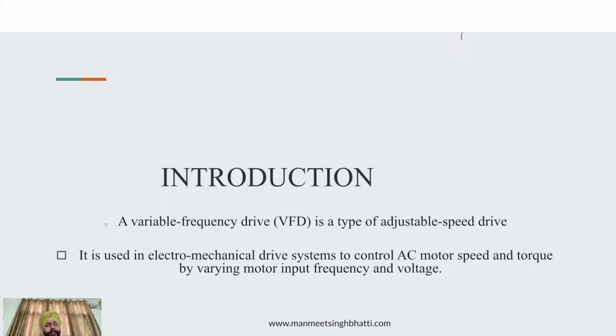As the name suggests, it is going to change the frequency of the complete power which is being given to your AC motor, and that way it is going to control the speed. So a variable frequency drive, as the name suggests, is only going to change the frequency of the power. Based on that, the speed of the motor is being controlled. So that's the basics of the variable frequency drive.